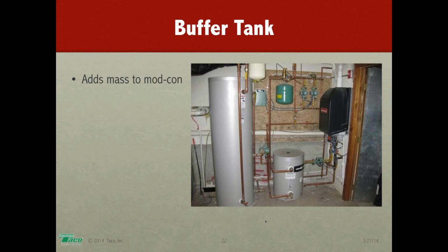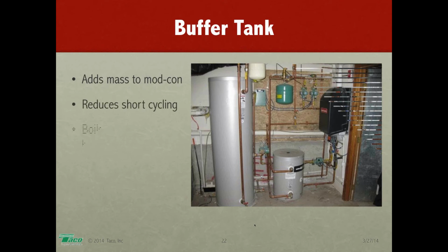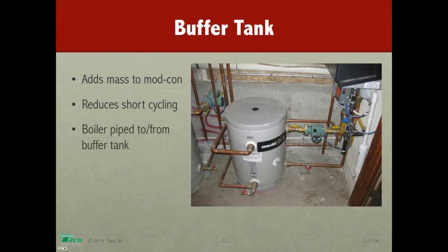So buffer tanks are just simply big hydraulic separators, but they pack a big wallop too. They help reduce short cycling, and as you can see here, it's just like a hydraulic separator. You've got your boiler supply, boiler return. You've got your system supply here, and your system return here. Works just fine. And the zone supply and returns, boiler supply and return, it's just a big old open space in the piping, big old tank, just like a hydraulic separator.